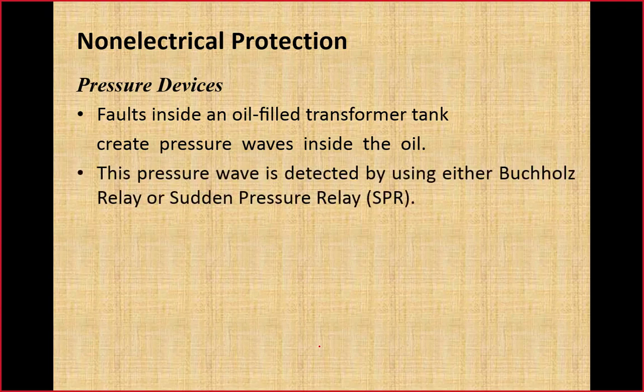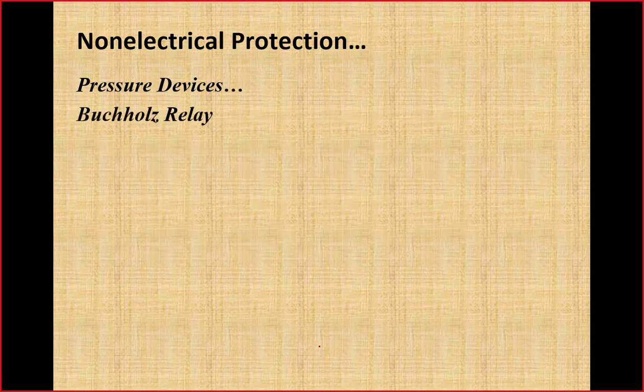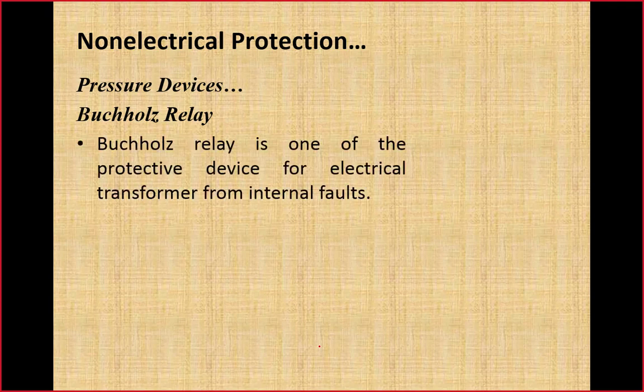So this pressure wave is detected by using either Buchholz relay or sudden pressure relay, SPR. Both these relays have working principle based upon non-electrical phenomena. So let's first discuss the Buchholz relay. Buchholz relay is one of the protective devices for an electrical transformer for internal fault, and it is very sensitive. So in the presence of Buchholz relays, differential relay will act as backup, and for internal fault, Buchholz relay is considered as the primary protection.